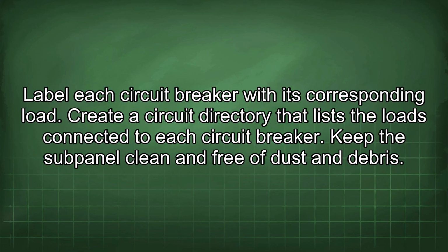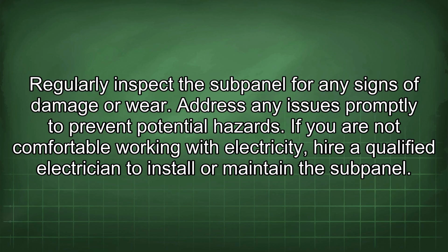Label each circuit breaker with its corresponding load. Create a circuit directory that lists the loads connected to each circuit breaker. Keep the subpanel clean and free of dust and debris. Regularly inspect the subpanel for any signs of damage or wear. Address any issues promptly to prevent potential hazards.